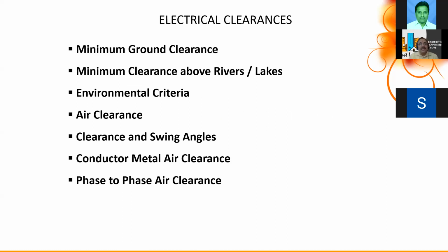Environmental criteria include air clearance and swing. We support the conductor with an insulator between the structure, and this insulator can swing. So when it swings, we consider different swing angles - 15 degrees, 30 degrees, 45 degrees - and then electrical clearance.